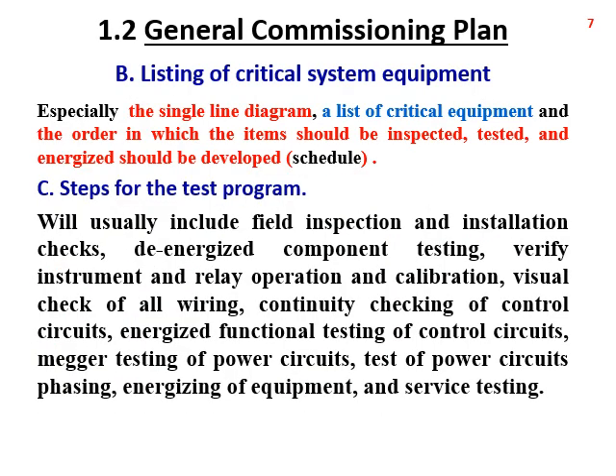General commissioning plan. B. List of critical system equipment, especially the single line diagram. A list of critical equipment and the order in which the item should be inspected, tested, and energized should be developed. Schedule. C. Steps for the test program will usually include field inspection and installation checks, de-energized component testing, verify instrument and relay operation and calibration, visual check of all wiring, continuity checking of control circuits, energized functional testing of control circuits, megger testing of power circuits, test of power circuits, phasing, energizing of equipment, and the service testing.